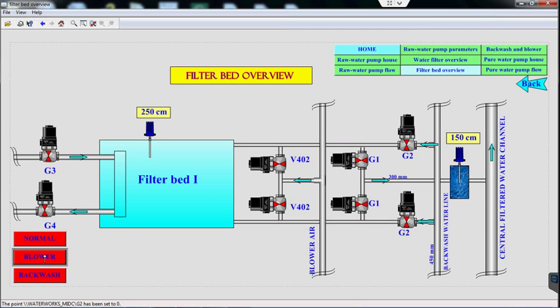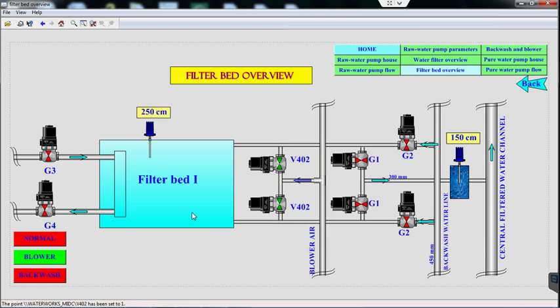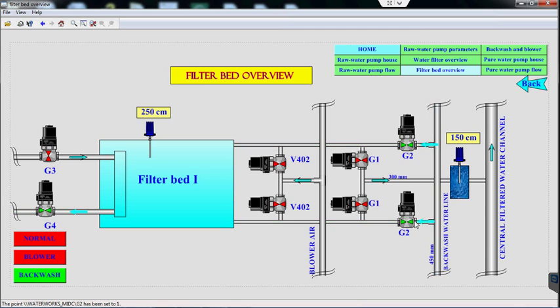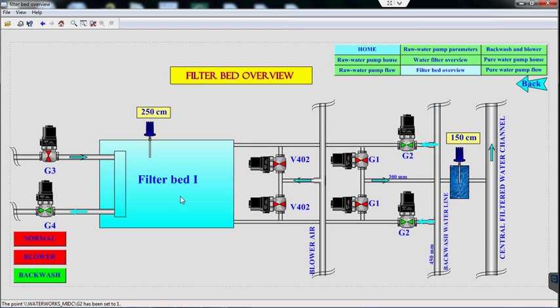The next sequence is blower mode. In this stage, raw water and pure water valves are closed automatically. Backwash water line valves are also closed, and blower line valves will automatically open. Air will fluidize the sand and separate the turbidity from the sand. After a predetermined time, the air valves will close and the blower sequence will stop. The third sequence is backwash mode. During the backwash cycle, all other valves will automatically close and the backwash inlet valve and drain valve will open. Pure water delivered from the backwash water tank will clean the filter bed. Turbidity separated from the filter bed will be carried away to drain. After a predetermined time, the cycle will stop and the normal sequence will start.